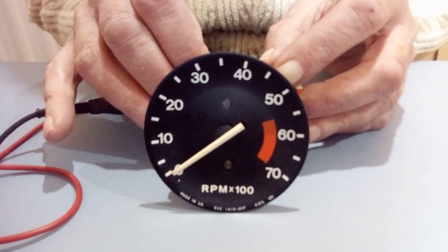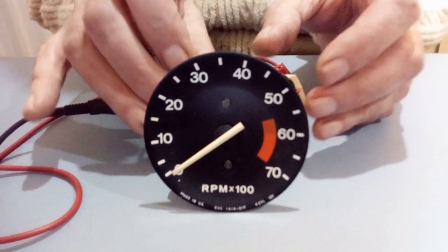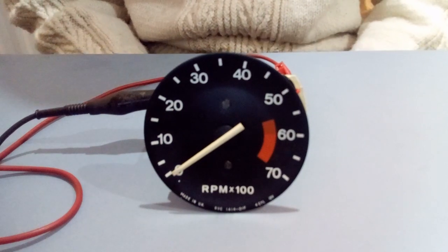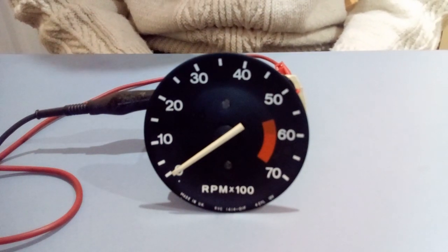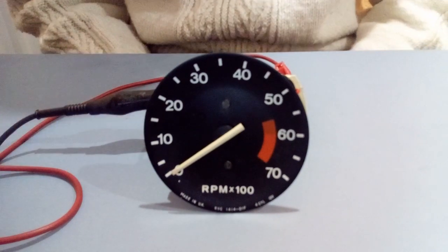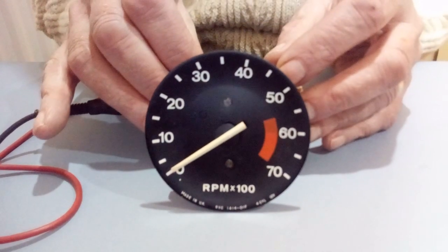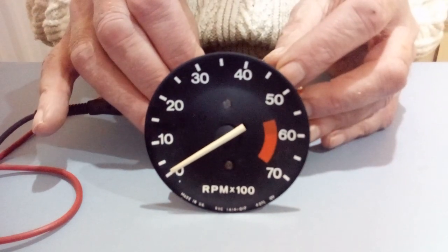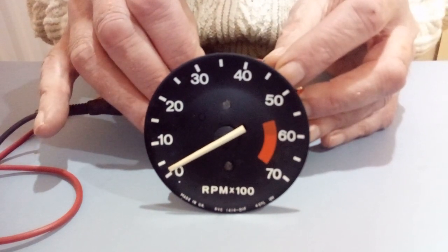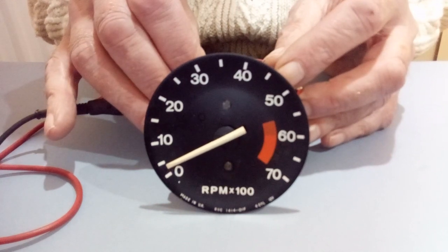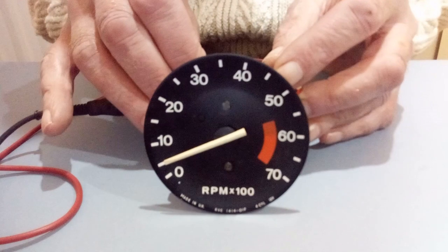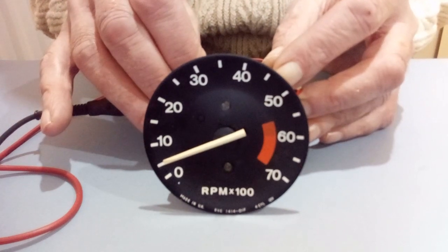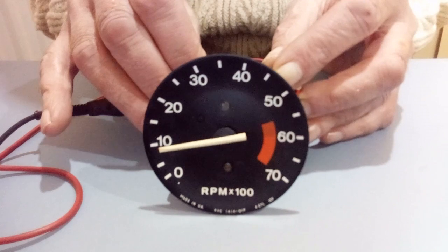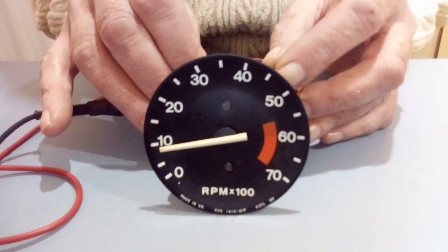So I've been holding the button in and I'm going to release it now. And we'll just wait and see the needle start to move. As I say, it can take a little time, and that really depends on your particular tacho. So we're just waiting now for it to start moving. And when it starts, there, it started now, and I'm going to hold the button down when we get to 500 RPM, which is the first calibration point. So we're just there now, and I'm holding the button down, and I'm waiting for a little kick. And when we see that kick, there it is, then we know the electronics has registered that point, and we can let the button go again and the needle will continue to move round.